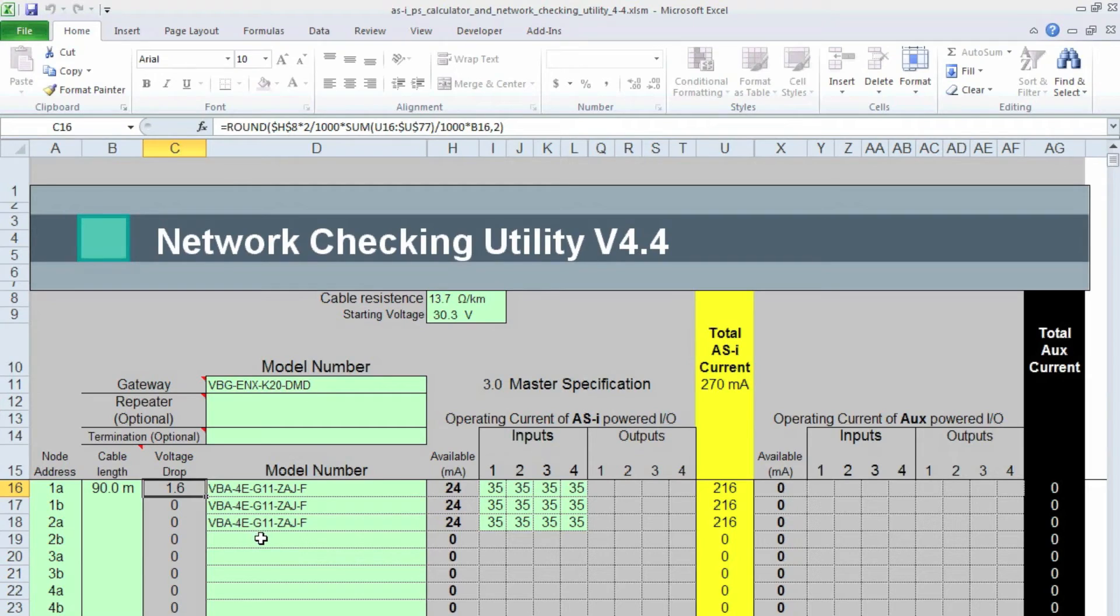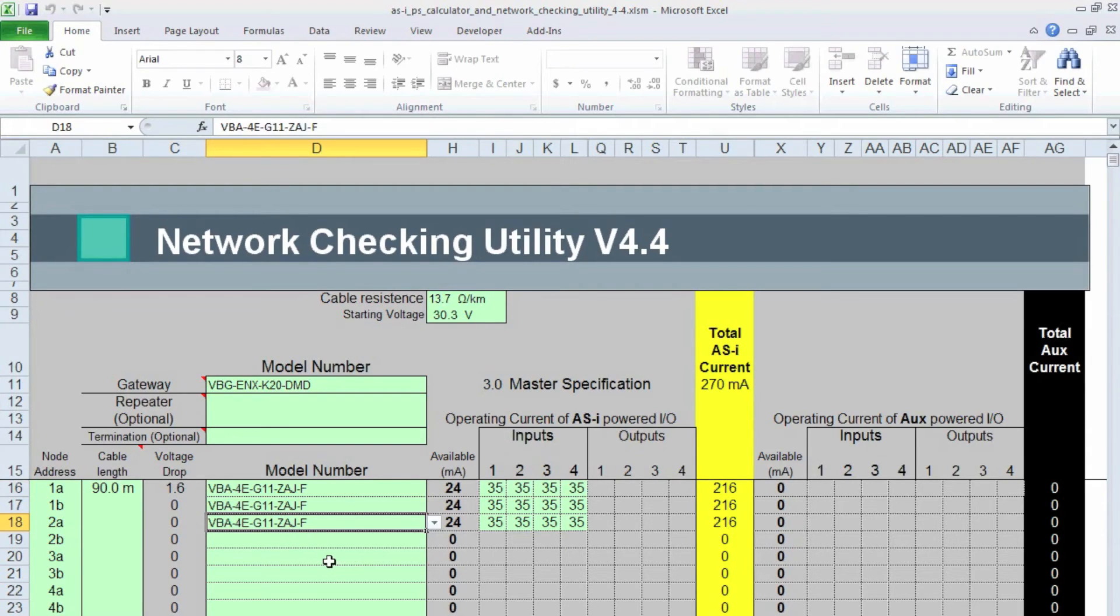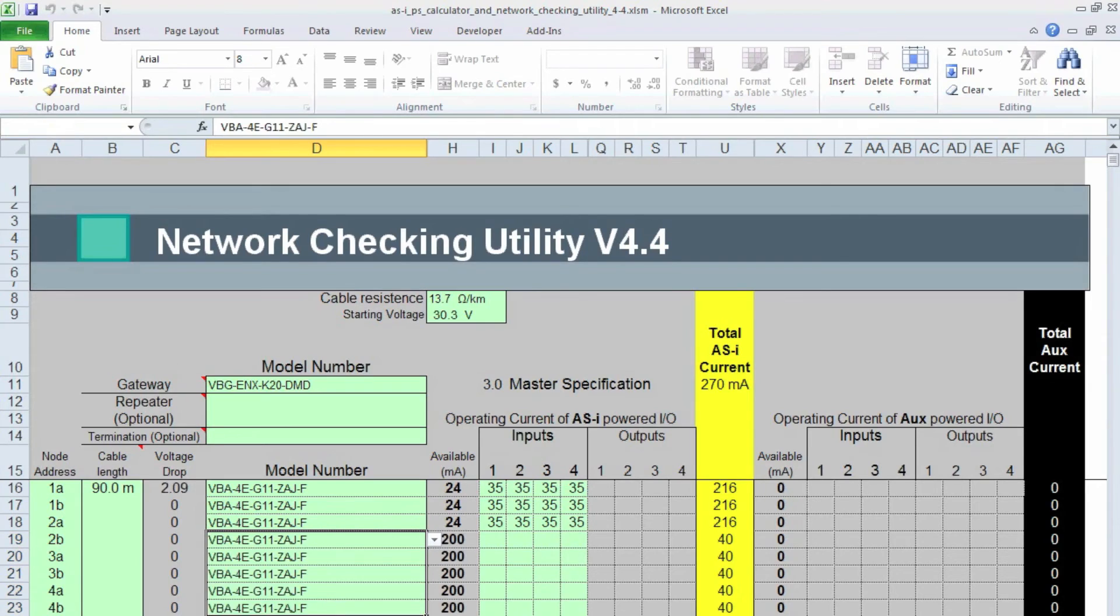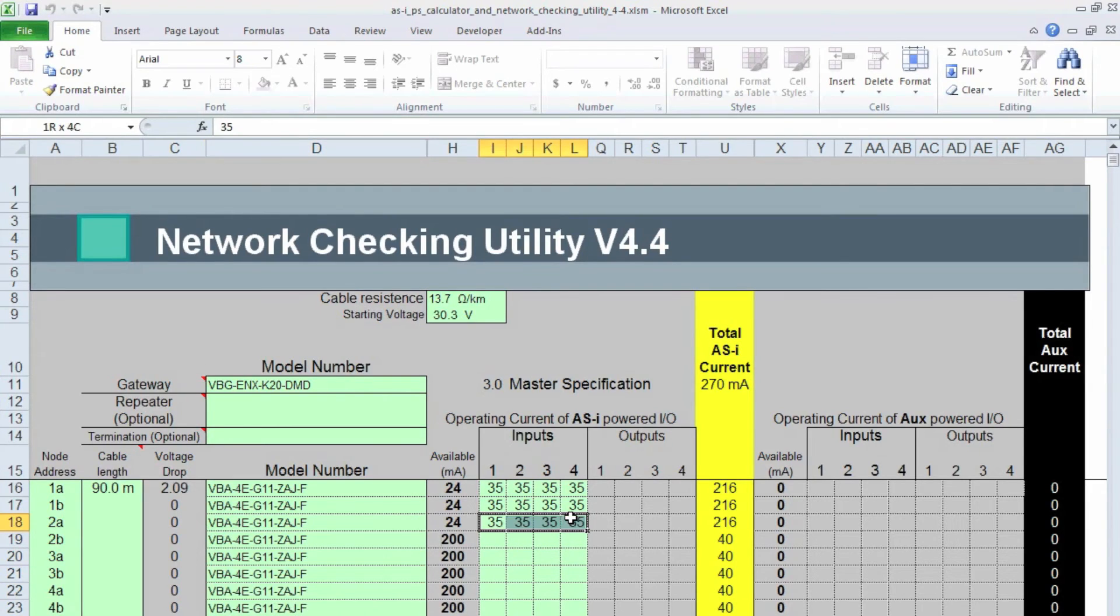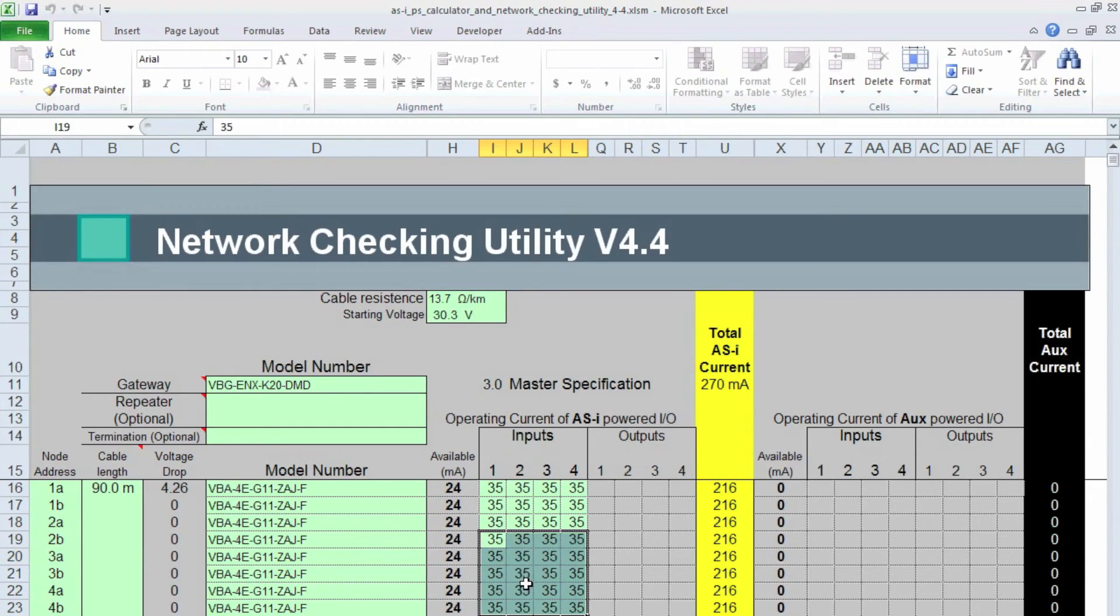Okay, so the next thing I want to do is see how many of these modules that I can put on the network before I exceed the 4 volt drop, or before I go below the 26.5 volts at the end of my cable. So I'm just going to copy and paste this. I think I can get maybe 8. We'll see. Copy and paste all these sensors. I'm assuming that I'm going to have the same sensors and they're always on on all the modules.